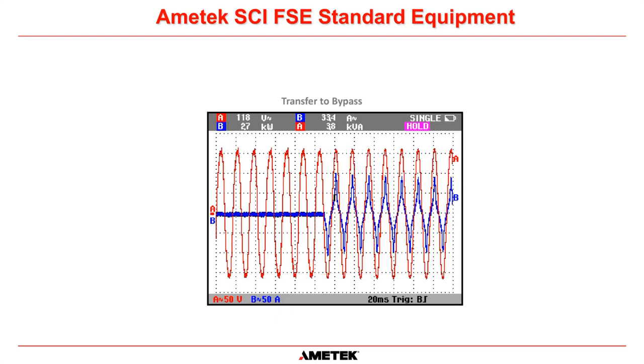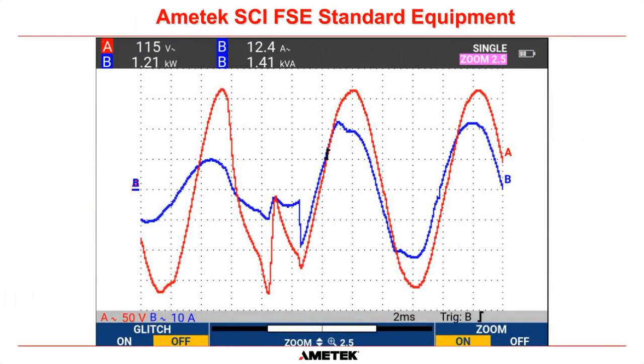And this next slide shows you a worst case scenario. This is the exact same scenario. We've transferred from inverter to bypass. So I zoomed in so you could see it. So this point here, this red waveform here, that's inverter. And this red waveform here is bypass. Okay. And what we did in this system is we actually crashed the inverter.